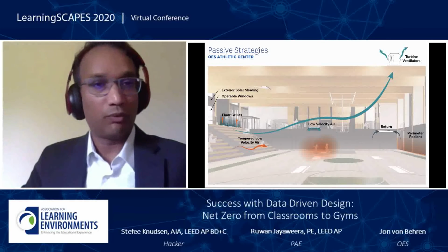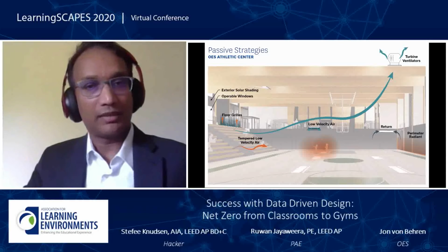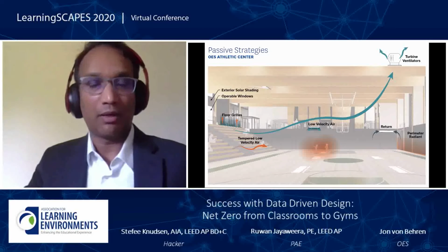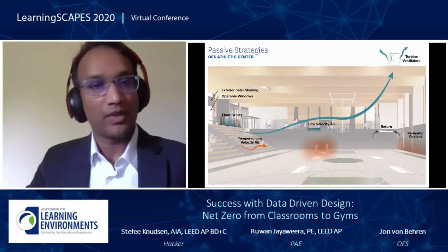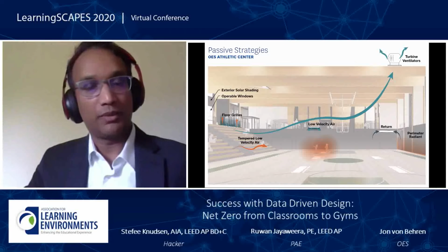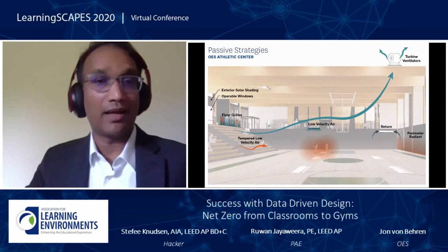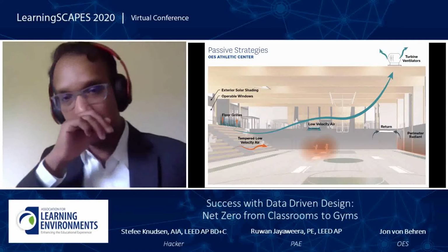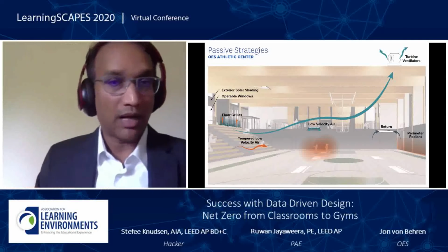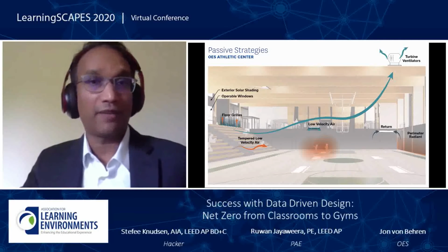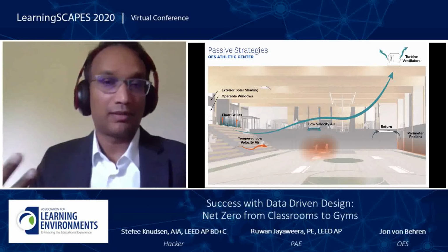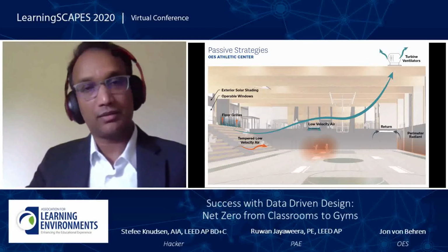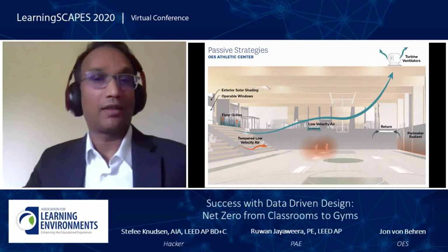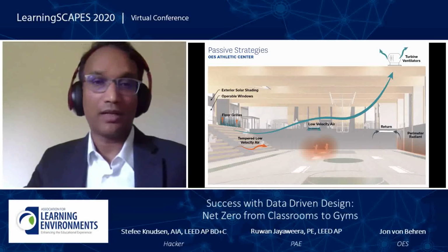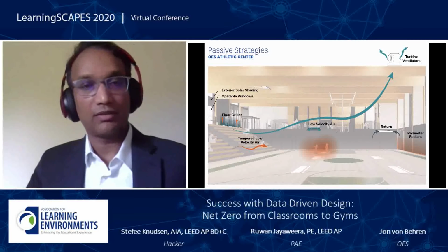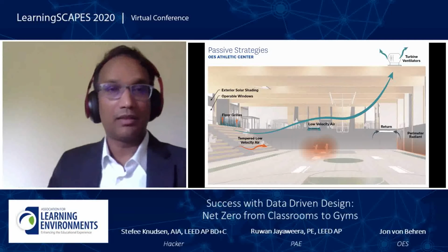I have to admit, when we first did this modeling, I was a little concerned because I wanted operable windows down at the playing level, to get air to that level. I thought the windows would open, air would come out, and it'd stay high and go out the turbine ventilators at the ceiling top. But once we started the passive cooling modeling, we found this was very effective. Since hot air rises and you get stratification in this high bay, this approach took out all that stratified hot air and allowed the playing floor to cool down. I learned a lesson in the modeling on that one too.